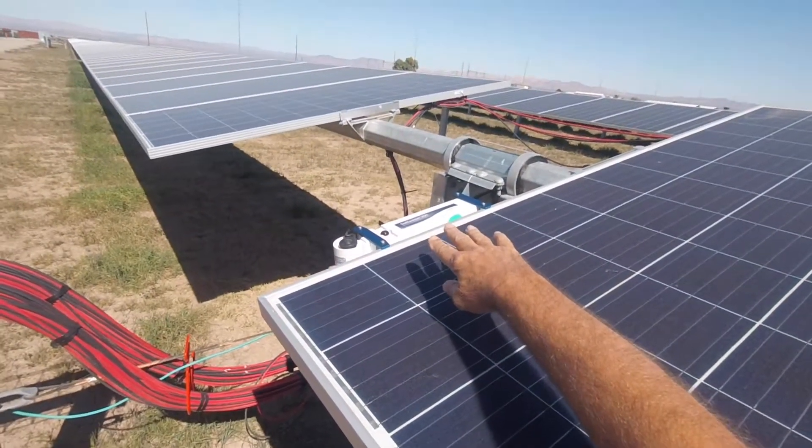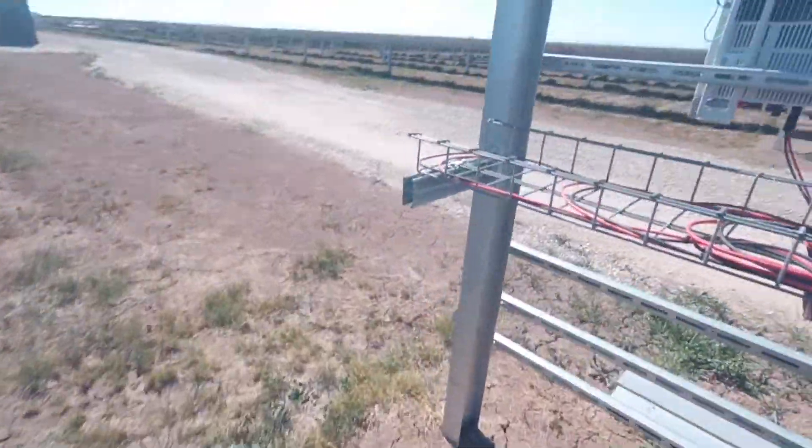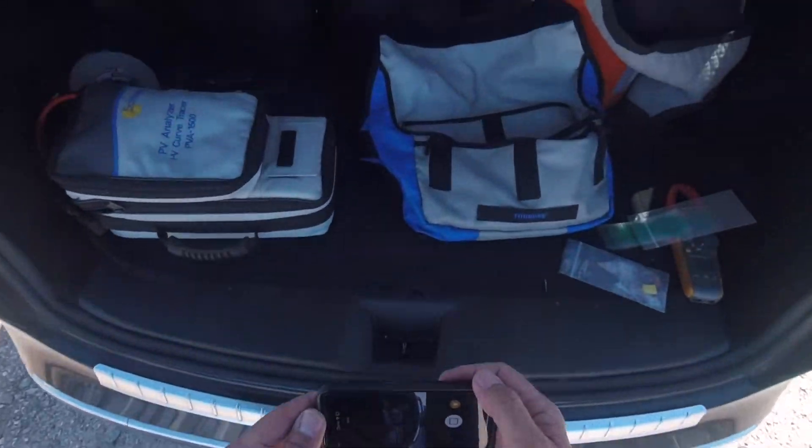So that's ready — it's going to measure the angle of the array, the irradiance in watts per square meter, and the back-of-module temperature, and then send that data to the software instantly when it takes the measurement. All right, back at the car — we just mounted the solar sensor on the array.